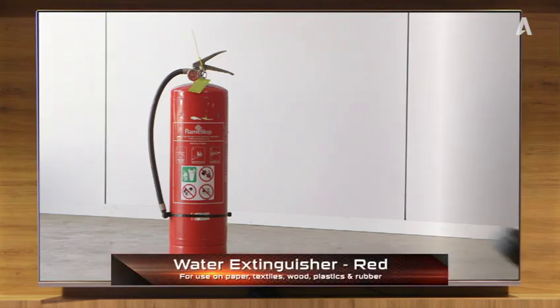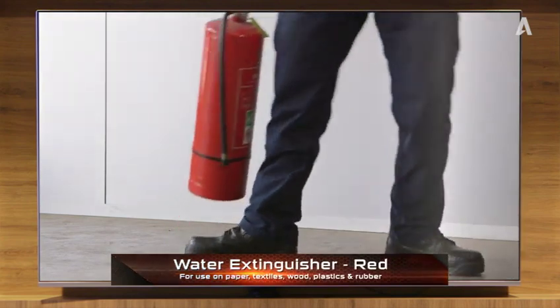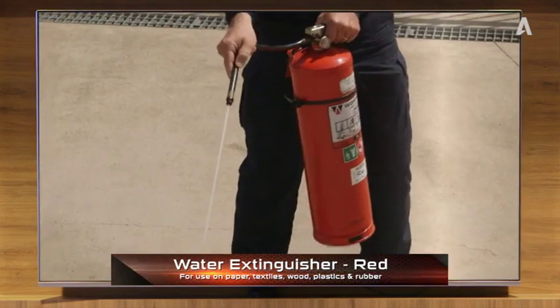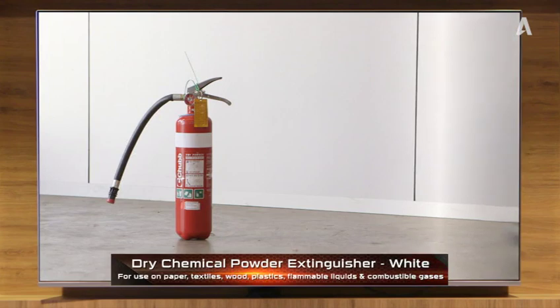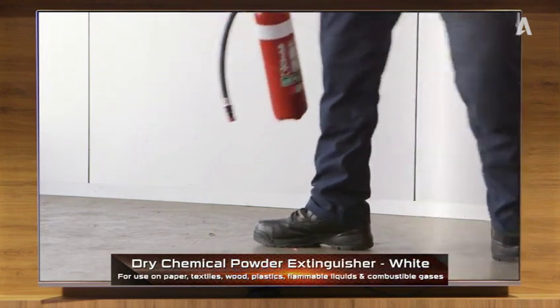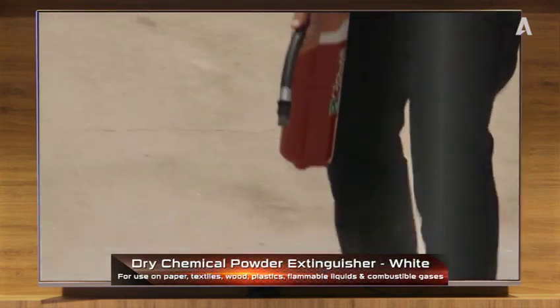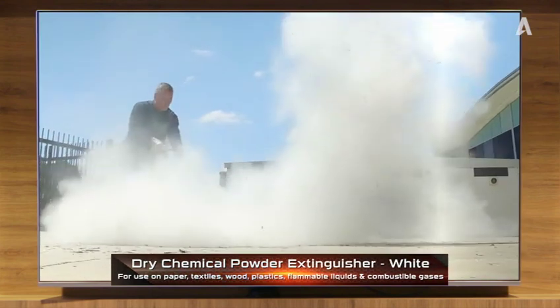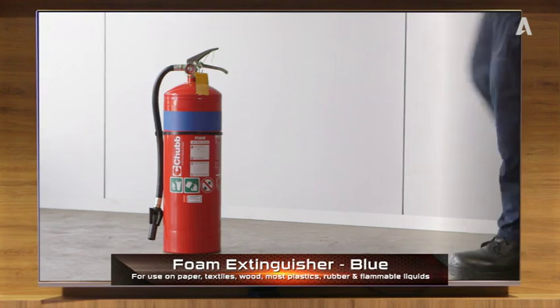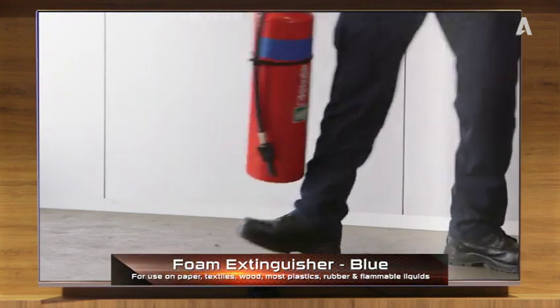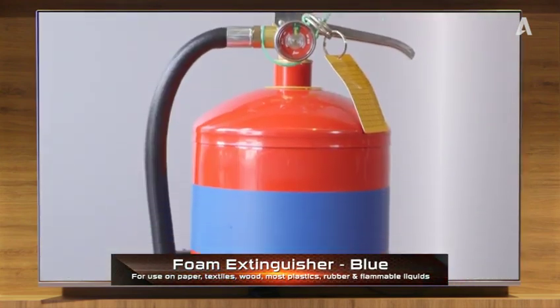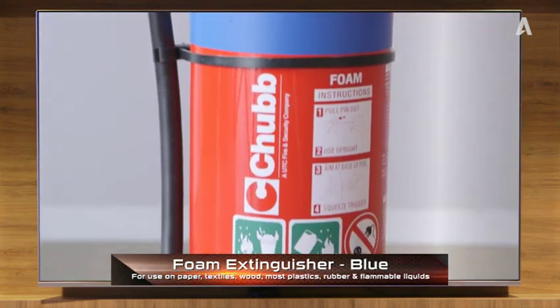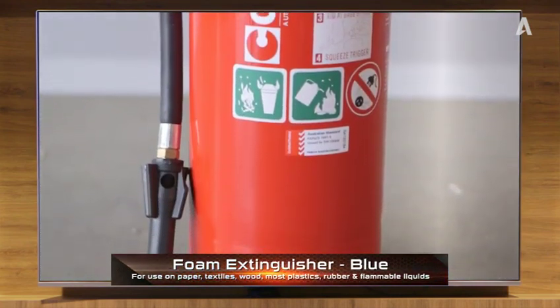As I mentioned, there's different colour-coded extinguishers for different types of fires. This water extinguisher is good for paper, textiles, wood, plastics and rubber. A dry chemical powder extinguisher has a white band. It's suitable for paper, textiles, wood, plastics, flammable liquids and combustible gases. The blue band means a foam extinguisher. It's suitable for paper, textiles, wood, most plastics, rubber and flammable liquids.